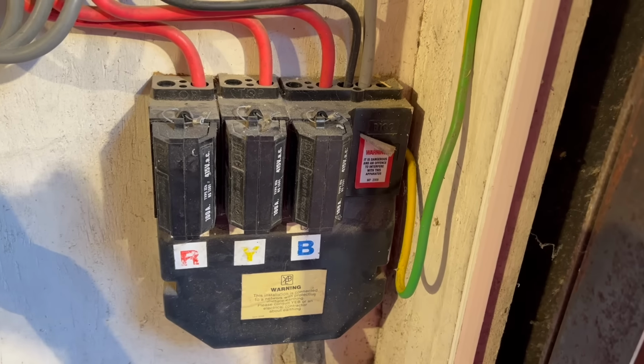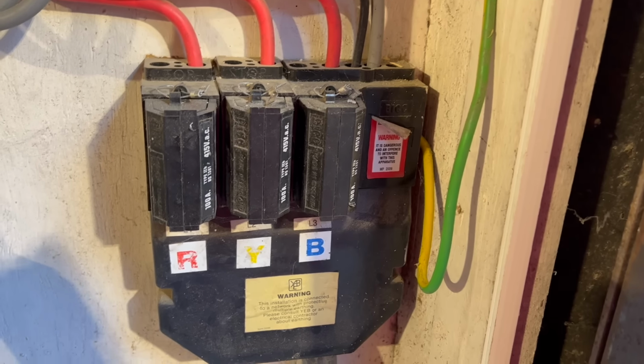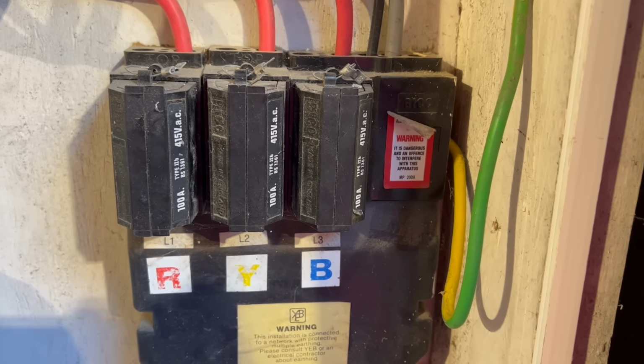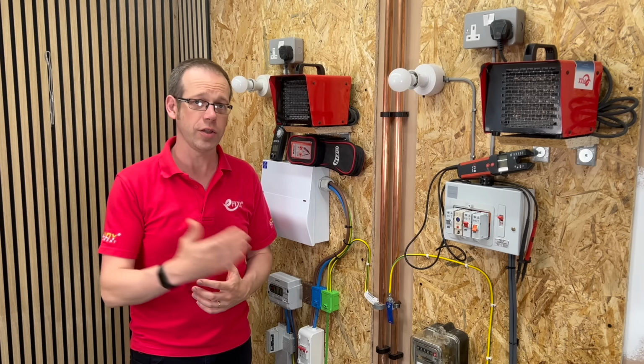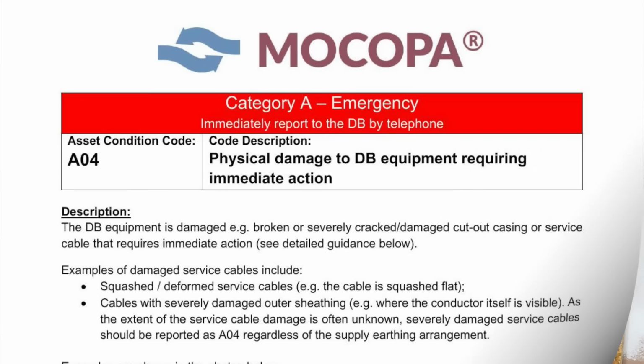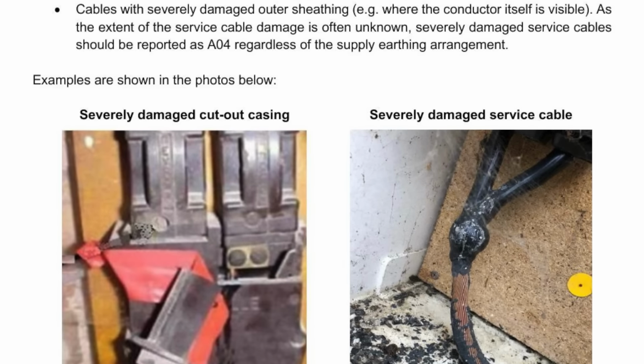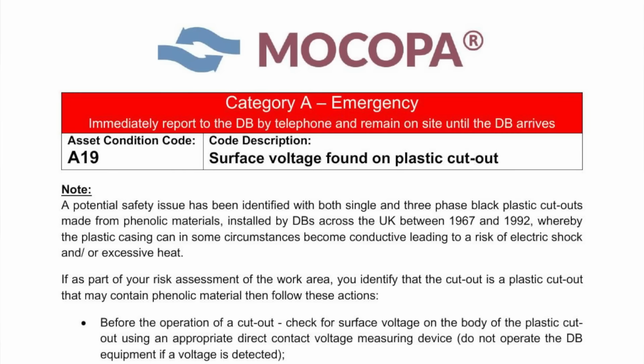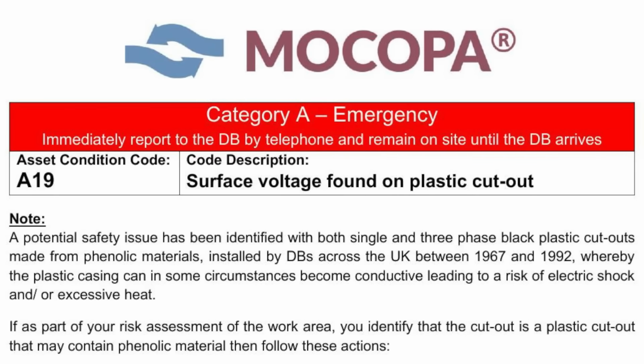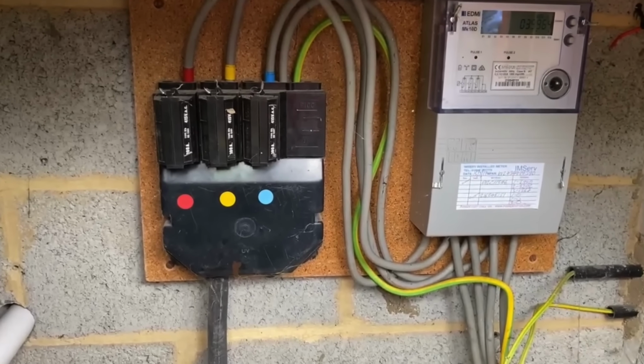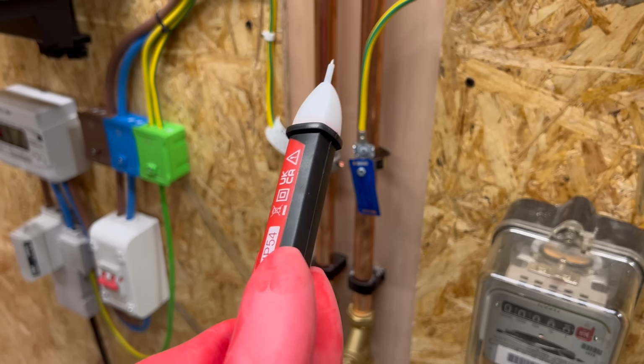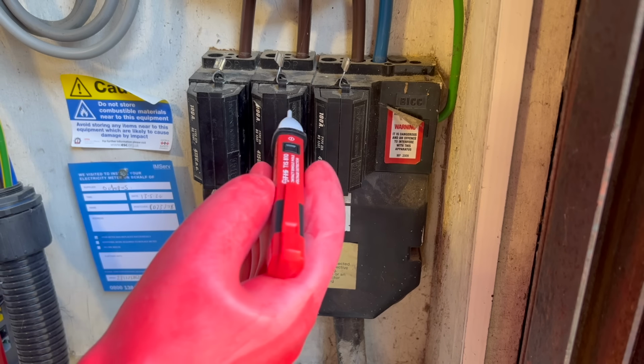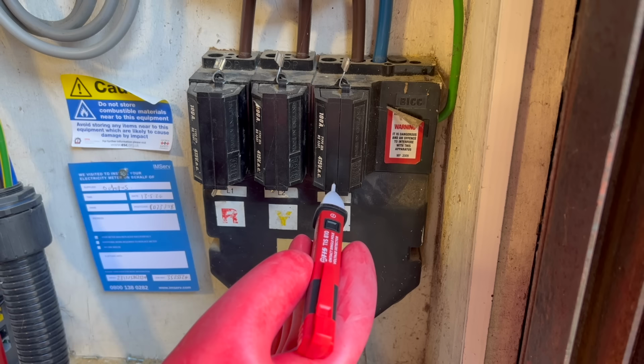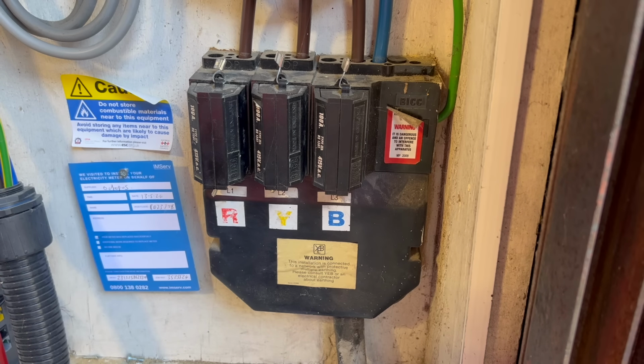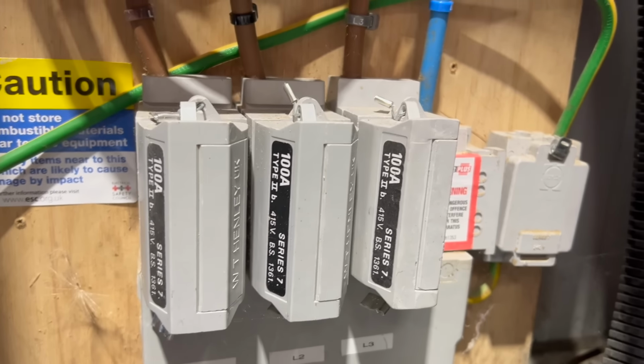Older service heads, particularly those installed during the mid-20th century, often use casings made from what's called a phenolic resin. Over time, exposure to heat cycles and environmental factors like moisture and UV radiation causes the phenolic material to degrade. This can lead to embrittlement and even cracking, exposing live components. Even more dangerous, and extremely surprising, is that the plastic type material itself can become conductive and therefore live under certain circumstances. If you come across older black coloured service heads, then grab yourself a voltage contact indicator like this one from TIS and check all the different parts of it, especially the parts you might need to touch like the fuse carriers. If at any point it shows that the surface is live, then contact the DSO for that area. The more modern grey cutouts are a different material and are not prone to this type of issue.